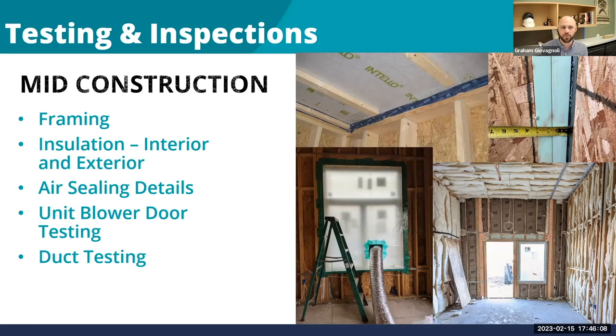And then we do duct tightness testing to give valuable feedback, because if the ducts are not tight, then TAB is really hard to do, and it's very hard to get CFM to the places where the designer has intended it to go.